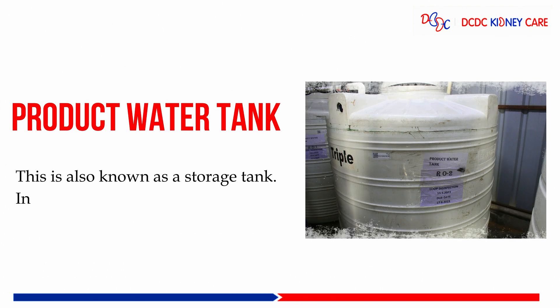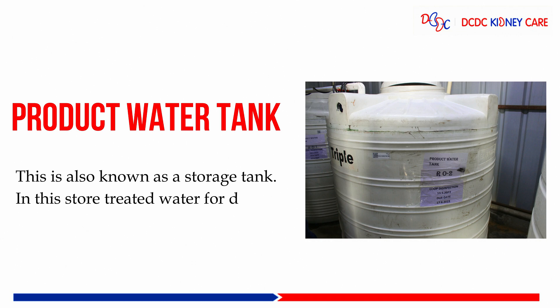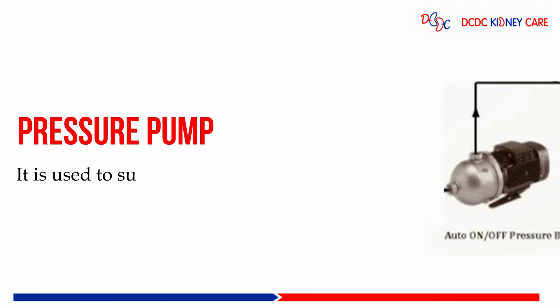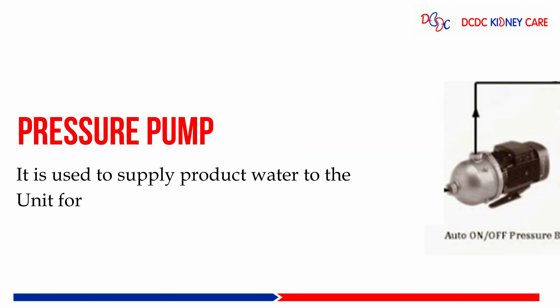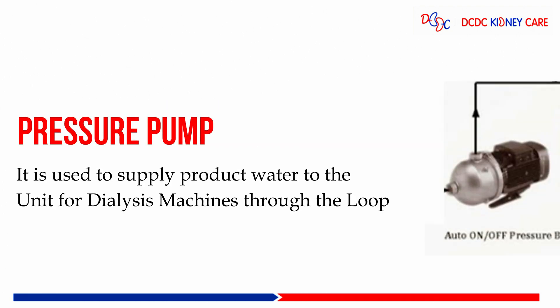Then the product water tank, also known as the storage tank, which stores treated water for dialysis. Then the pressure pump, which is used to supply product water to the dialysis machines through the loop line.